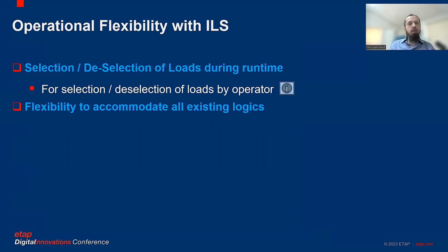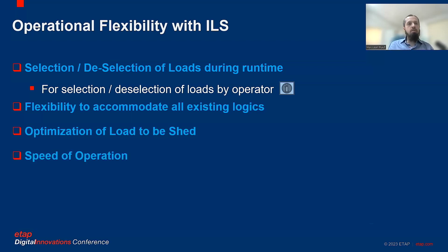Then the system was flexible enough to accommodate all the existing logics, which is a key requirement in any brownfield or retrofit project. Optimization of load to be shed: definitely, with all the automatic load shedding and the real-time monitoring, the load to be shed against a trigger was optimized. And finally, the most critical aspect of any load management system is its speed of operation. So naturally, the ILS in its construction is like this. All the calculations are done while the system is running, and based on the calculations and the system conditions, the load shedding table is uploaded into the PLC. So at the time of a trigger execution, our PLC already has all the information which it needs, and there is no runtime calculation involved. As a result, the speed of operation is quite fast compared to other software solutions.